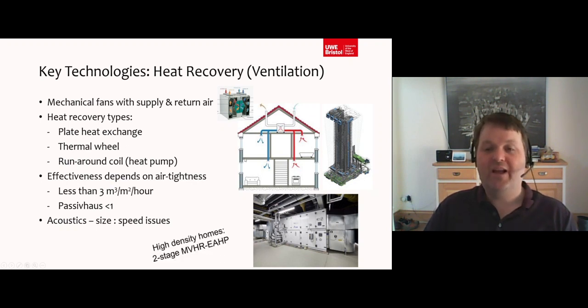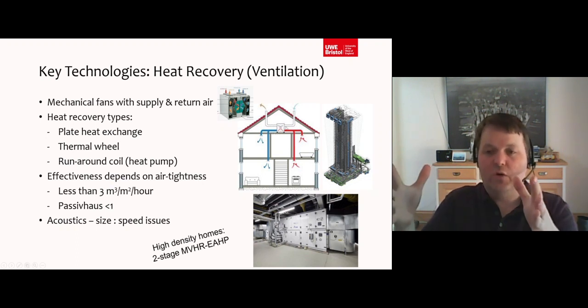And the last thing I'll say about MVHR, if you've watched the heat pump video as well, there is a very interesting piece of research that was published there in the November 2019 version of the CIBSE journal, which compared all the options for high density residential living, so apartment blocks and things like that. And the kind of runaway solution was an MVHR, where you're taking heat out of your return air, but then having a second stage on here, whereby you have an inbuilt packaged unit. The whole thing is a packaged unit, a heat pump that is then pumping heat from your exhaust air into the fresh air as well.